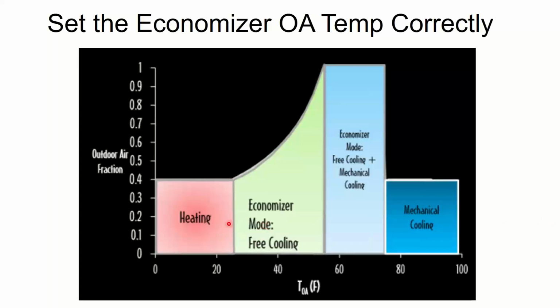As far as ventilation rates go in a building, look at this chart. This particular example is a 40% ventilation rate system, so I'm at 0.4. That's the ventilation rate I have to bring in whenever it's occupied. I bring that in during all the heating hours and all the cooling hours in summer. But in spring and fall, or on any mild day in summer, I'm going to open up the economizer damper and bring in more free air for cooling.